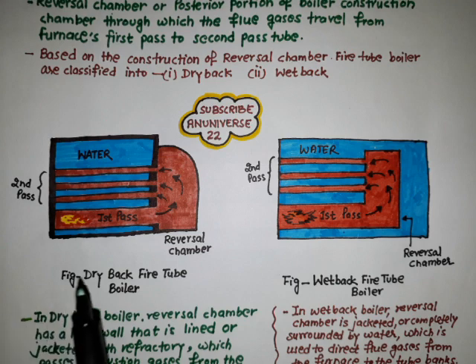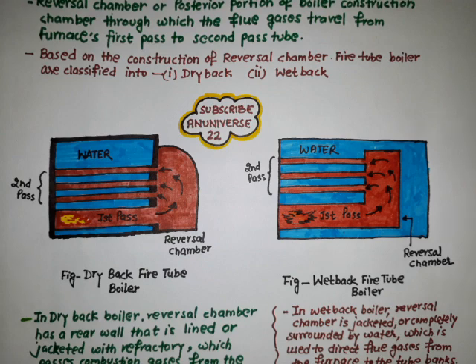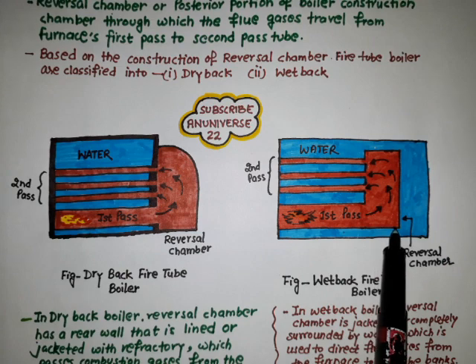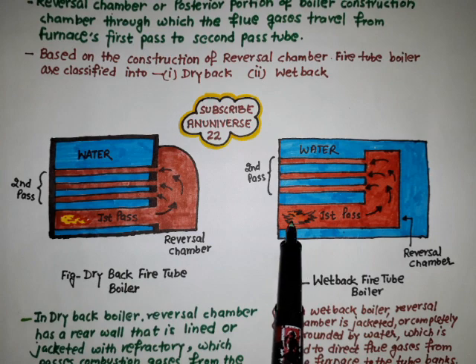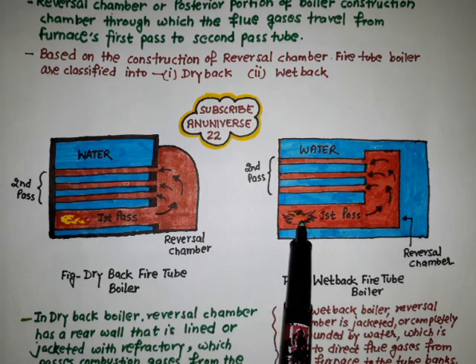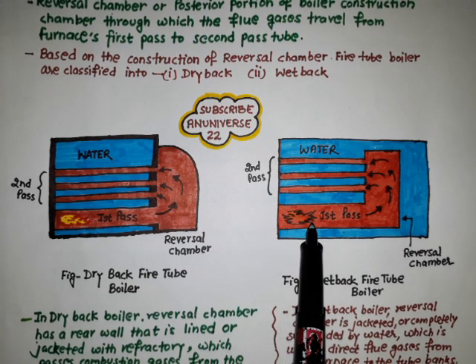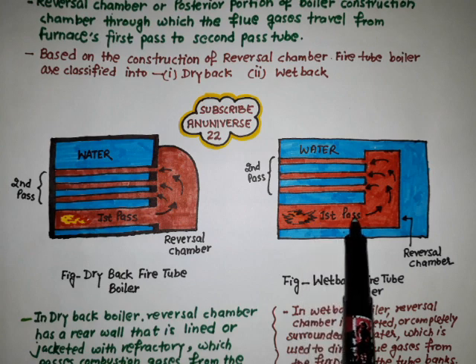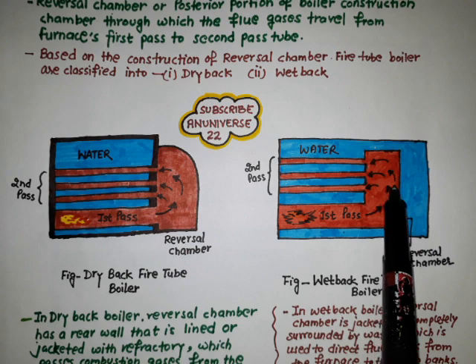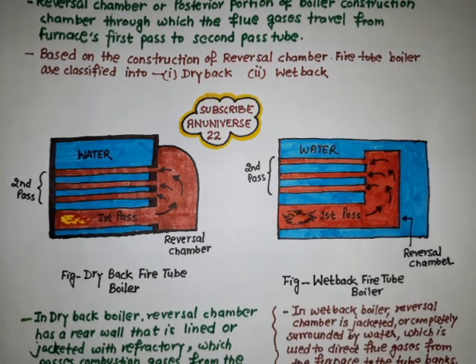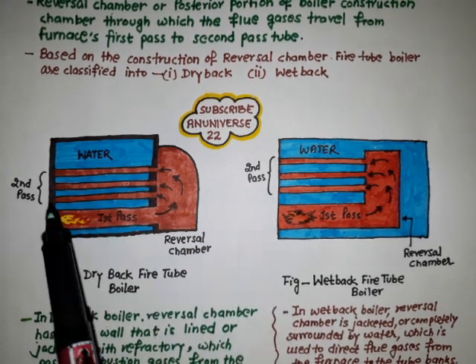The frustrating problems brought by the dry back fire tube boiler can be resolved by the wet back fire tube boiler. In the diagram we can see the reversal chamber of the wet back fire tube boiler. These are the flue tubes, and this is the furnace. After burning of the fuel, this is the first pass of the flue gases, which are collected in the reversal chamber, and from the reversal chamber in the second pass they move to the flue tubes.